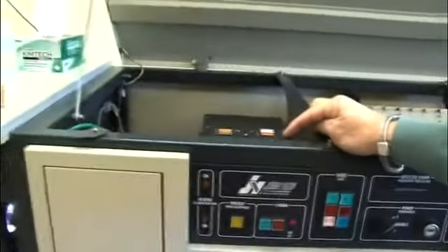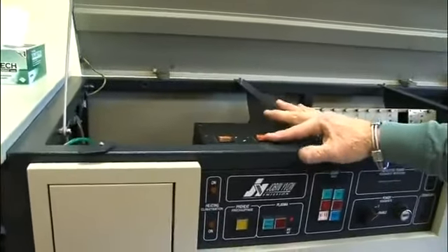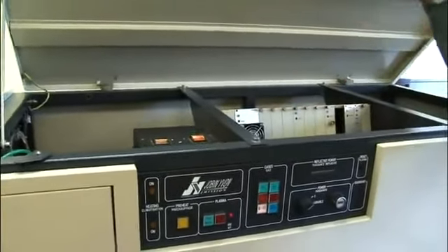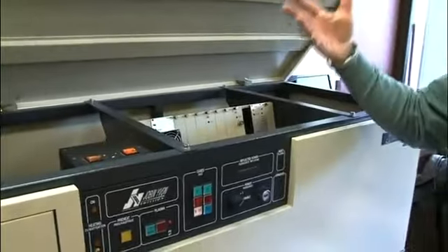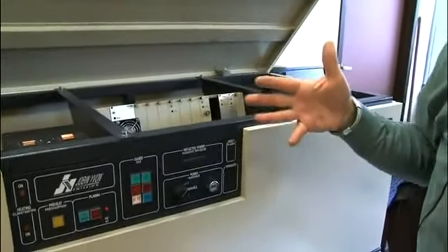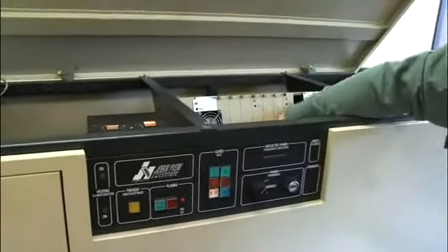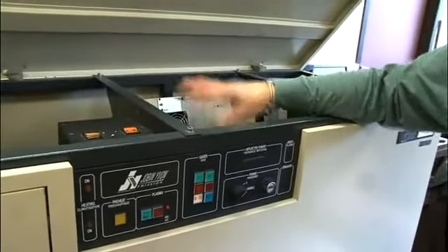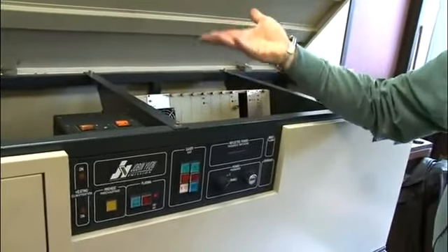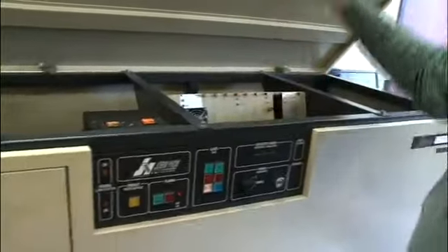This is a climate control. I only leave on the one for the monochromator. If you have large temperature swings in the room, it's going to affect your results. The optics will shift just a little bit. So they have a heater underneath the optical box to keep the optics at a temperature like 5 degrees higher than room temperature, like 30 Celsius.